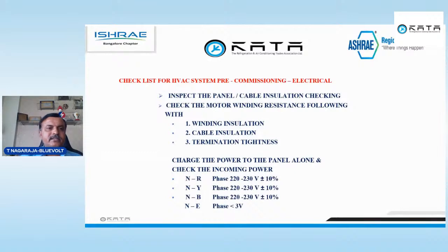Then a small hint I want to give: a checklist for HVAC system pre-commissioning. Electrically, inspect the panel, check the cable insulation, check the motor winding resistance, followed by winding insulation and cable insulation, then whether all the terminations are tightened or not. Then charge the power to the panel alone, only the panel. Check the incoming power without switching on the outgoing.